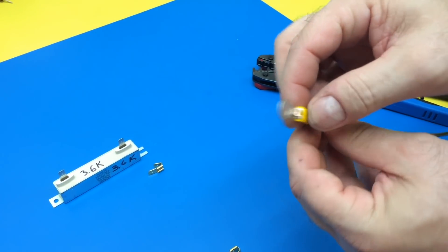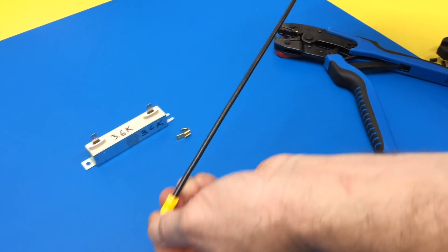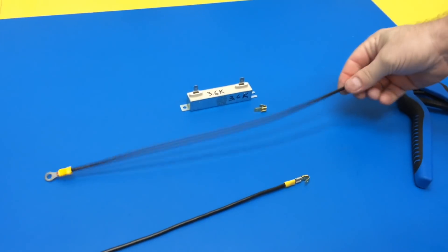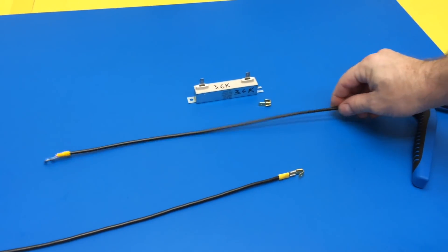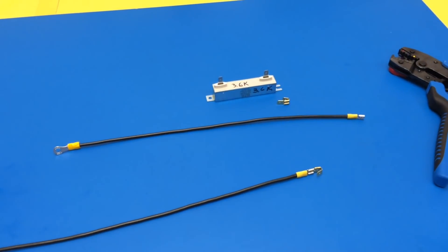And you can see it actually crimped to the insulation for a little bit of strain relief, and then we have a real solid crimp right there. It's real tight, so you definitely want to tug on each side. This will be real low current - it's just to balance both sides of the capacitor bank.